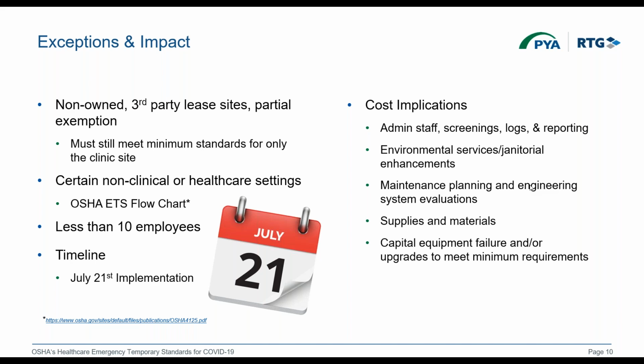I suspect for everybody, because they've asked us now to upgrade all this equipment to its manufacturer's specifications, and we've been running what I'll call MERV 8 filters for a long time. And so now we're going to go back, it's old equipment, and we're going to ask it to run at its original quality. And by the way, we probably haven't maintained it as well as we could have. And so now we're going to ask it to run in its original specifications, and the equipment is not going to handle it. That's a learning curve piece, but you're going to have to monitor the equipment, and you will see failures, capital equipment failures in the process. I think it's inevitable.